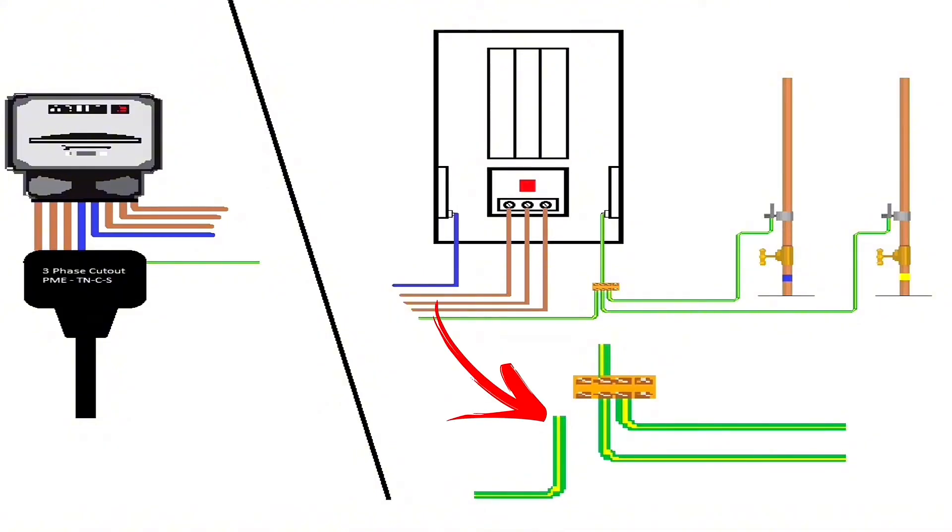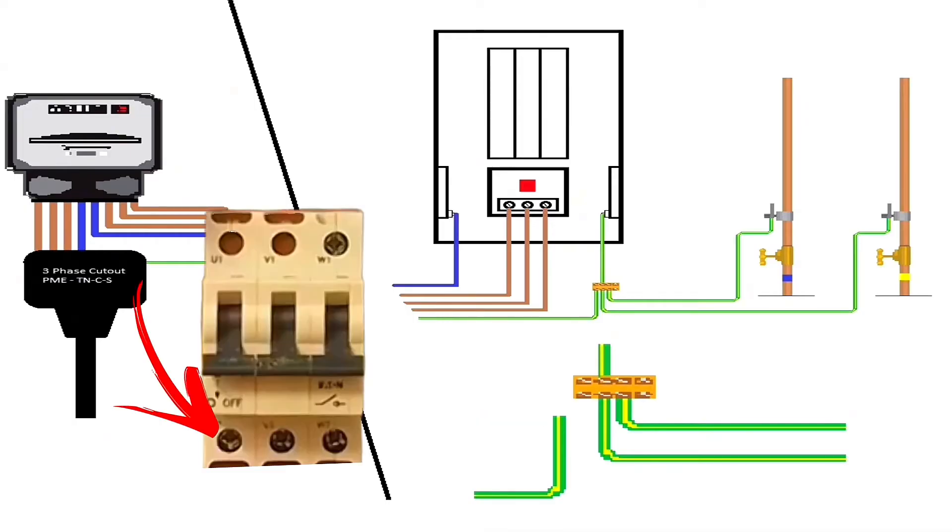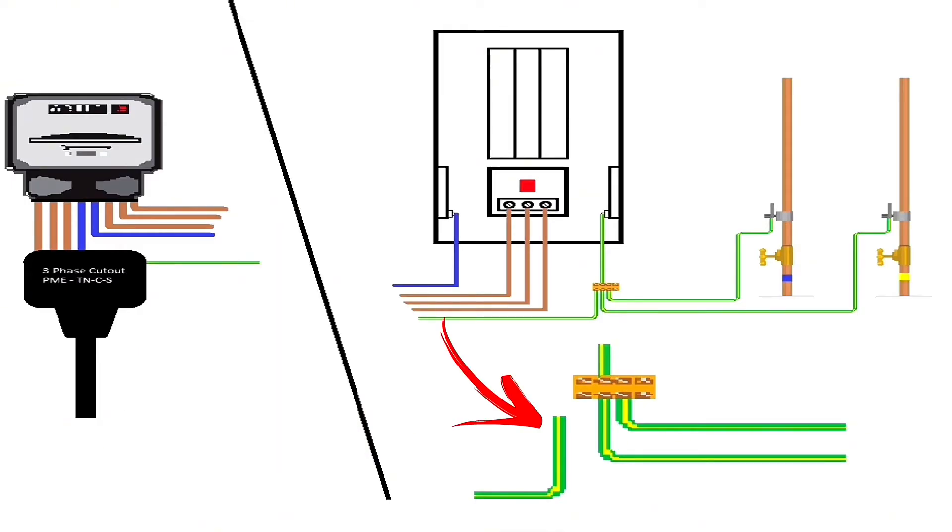Test from the disconnected earthing conductor to the board's individual lines to get our true external earth fault loop impedance. By removing it from the MET, you remove the parallel earth paths created by the metallic water, gas, structure of the building, etc.